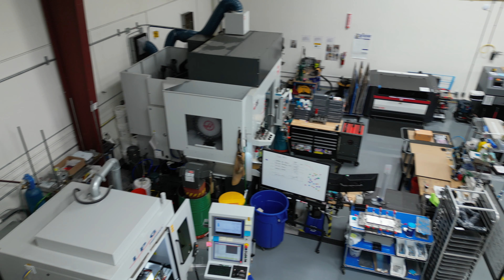Over here we have what we call our high pot system, or high potential testing. So we can test the electrical isolation between your high voltage domain and low voltage domain. One of the things for shock safety that's very important is that the battery cells themselves are electrically insulated from the case. So you never want to have your negative terminal or positive terminal or any interstitial terminals electrically connected to the case for shock safety. So one of the ways you check that is to make sure you have excellent isolation resistance and high potential withstand voltage between your high voltage domain and low voltage domain.